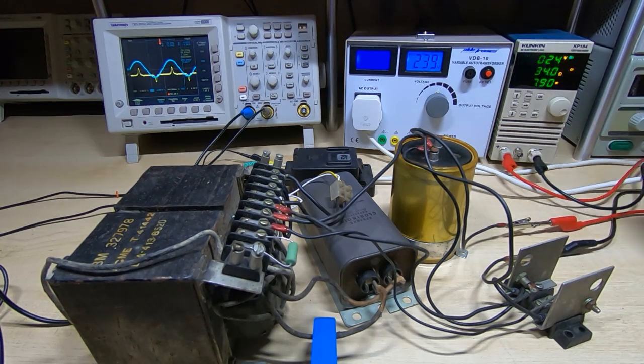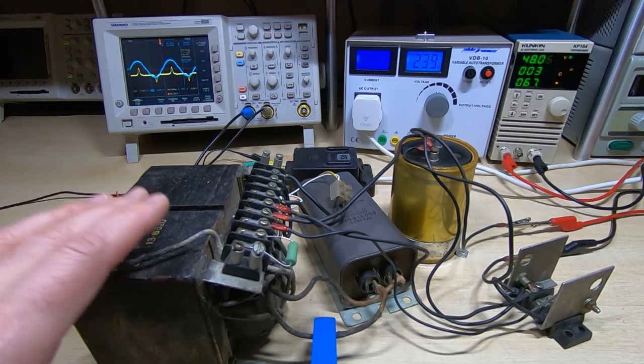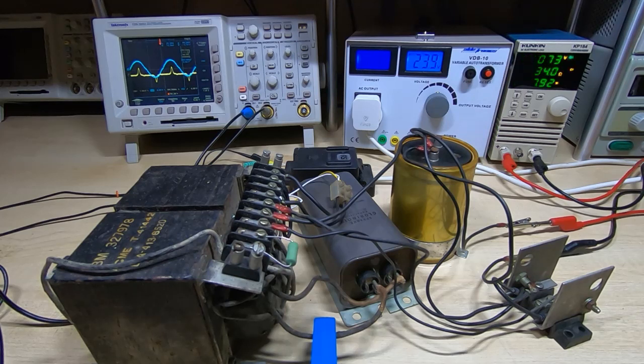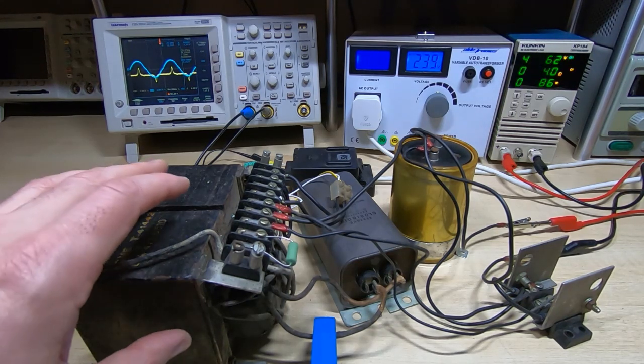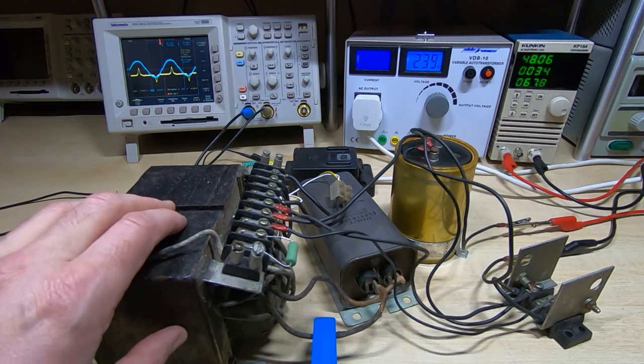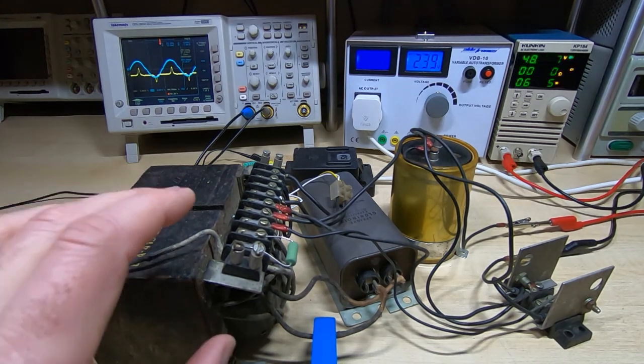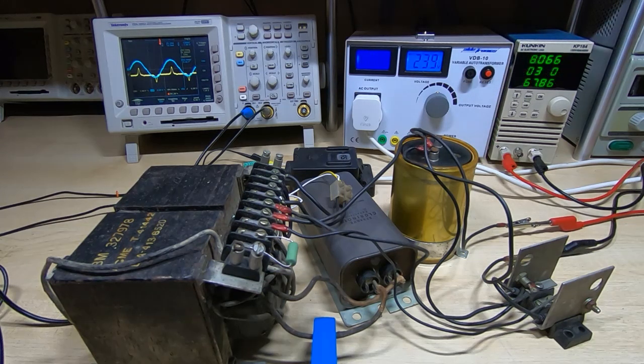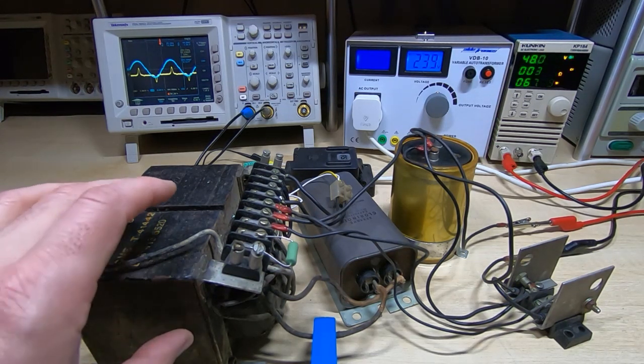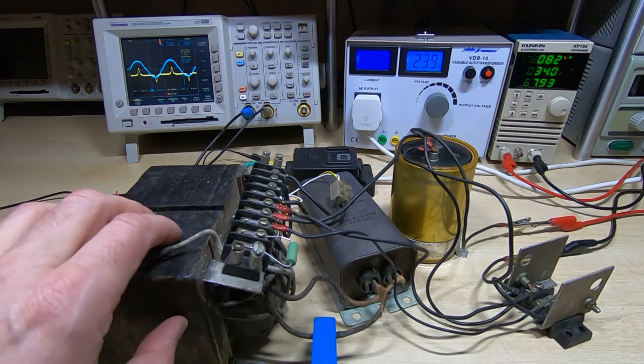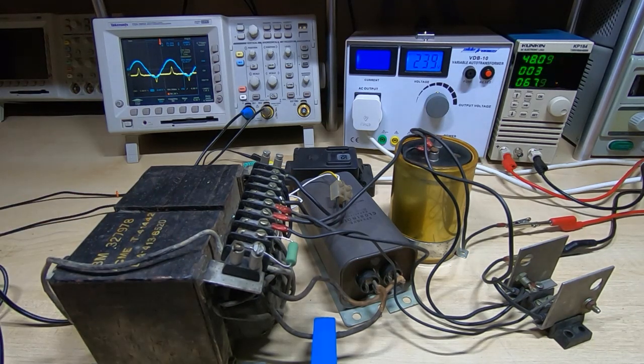That's as far as I went in the previous video. Now what we'll look at is the current waveform of the primary winding on the transformer. It's the current in the winding that dictates what the flux in the transformer core is doing, and because it's the flux that excites the resonance coil, that's what we're really interested in, since it dictates what the resonant circuit, and hence the output of the transformer, will be doing.